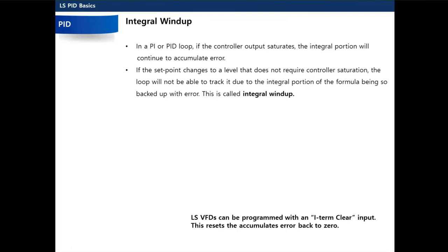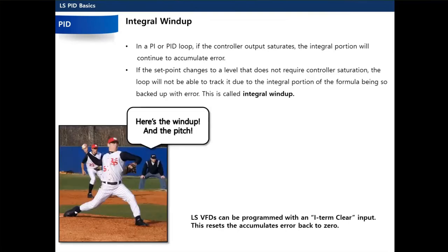So what we could do is use the I term clear input. Some drives have an integral limit where you can limit the integral. What we have is a digital input you can program, and you can put that switch on. Then you can reset your integral, and it's going to be a little more responsive because it's clearing out that error. It's clearing out that windup we're describing here.